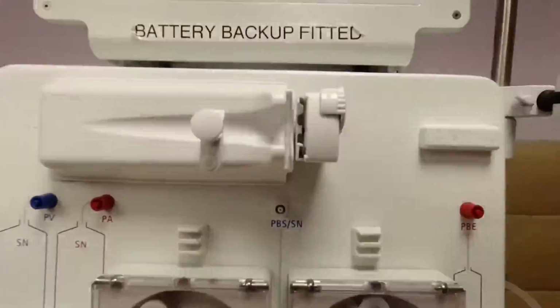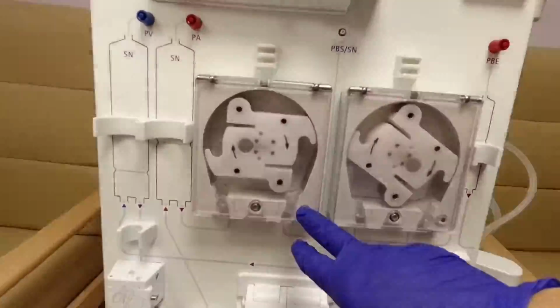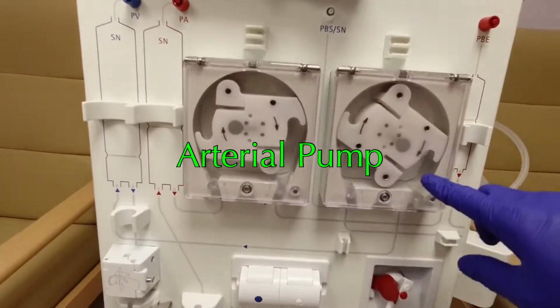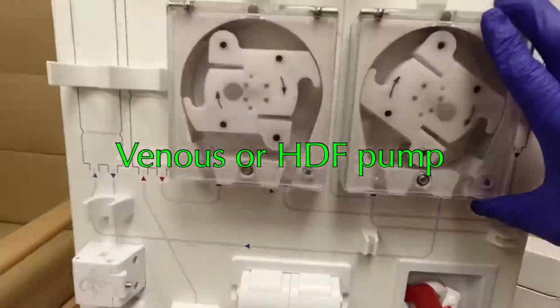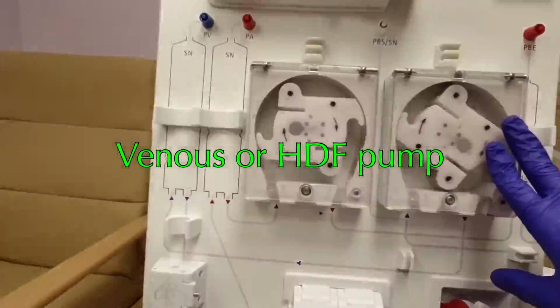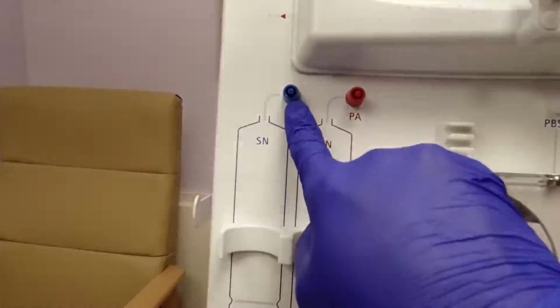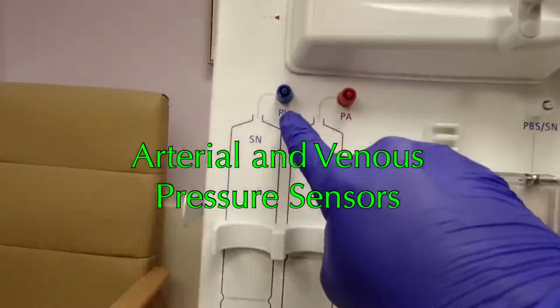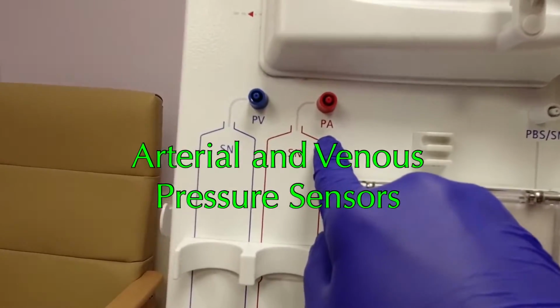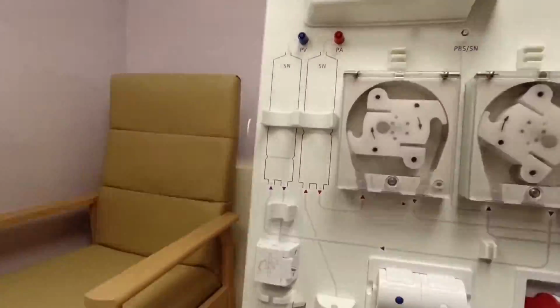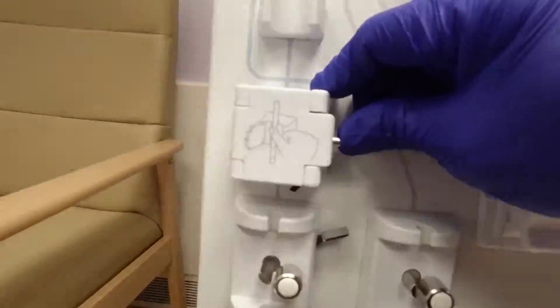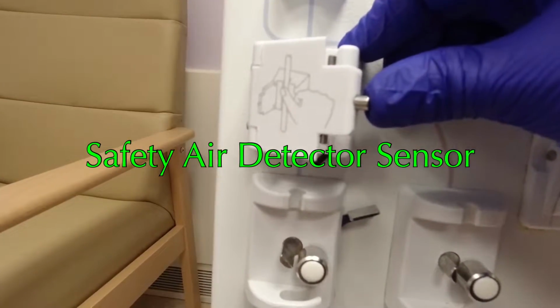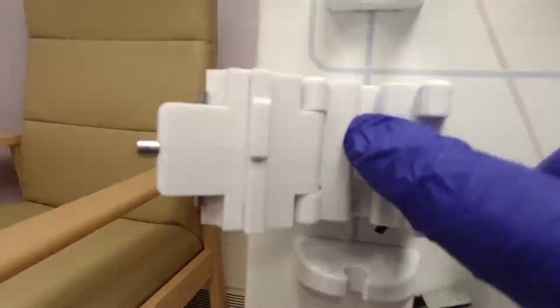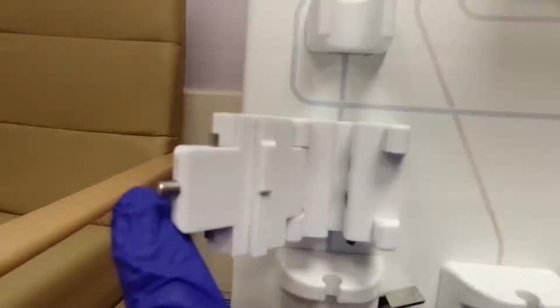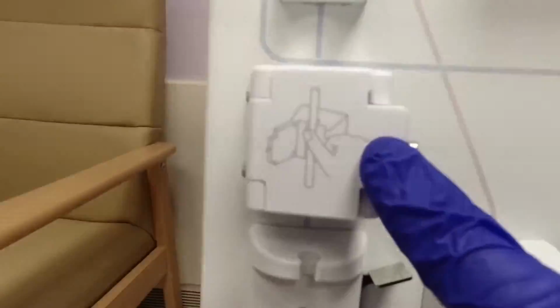Okay, right. So we've got two pumps in here. Got one for the arterial pump, and we've got one for the venous pump. Also, you've got the transducer pressures here for venous and arterial pressures. Also here you've got this safety air detector. So once the machine is on, there is a light in there and it detects any air that goes in. So just clap it, push, snap in there.